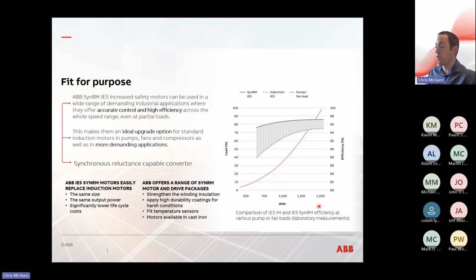So a typical 4-pole motor will run at 1500 RPM. And this graph just shows a direct comparison of an IE3 induction motor against a SynRM IE5. If you're running at lower speeds, say 750 RPM, which is 50% speed, you can see there's a significant improvement. You're talking maybe 6-7% efficiency saving due to using an IE5 motor in those sorts of circumstances. So it's an ideal upgrade option for standard induction motors on pumps and fans, and it will offer you improved efficiency and improved savings over the lifetime of the motor.